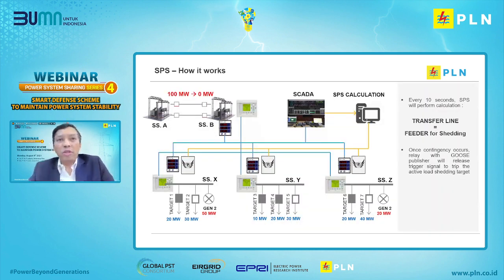How does this system work? We can see on the slide, let's say 100 megawatt is transferred from substation A to B. Every 10 seconds, the SPS server will perform a calculation based on data from SCADA to ensure that the amount of transfer is equal to the amount of feeder load that is ready for shedding. So this is a dynamic process. Every time the calculation is different. The higher the transfer, the higher the target load to prepare for shedding.